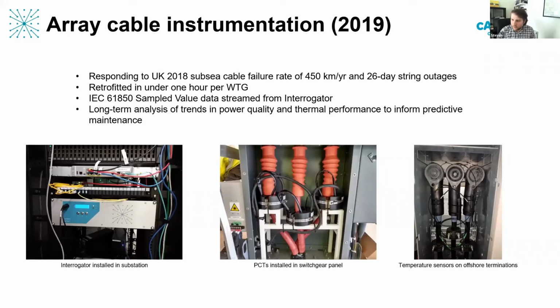Effectively, they don't need a power supply or a powered unit nearby to make them operate. They just connect to the fiber, and at a potentially large distance away, the interrogator unit is able to pick up those measurements. And then on the right-hand side, you can see the temperature sensors that we've attached to the cable terminations, just to monitor those.